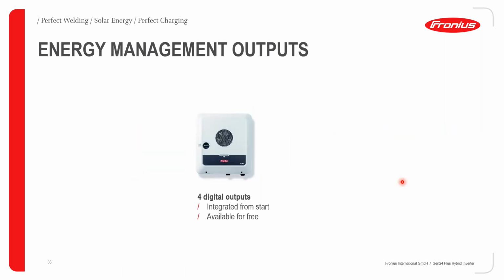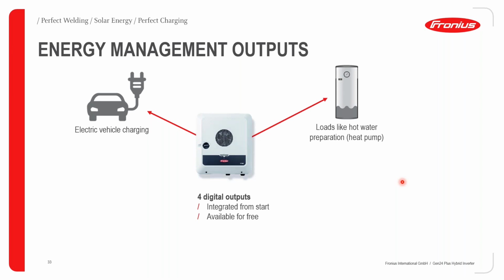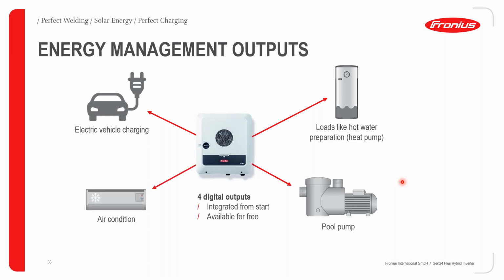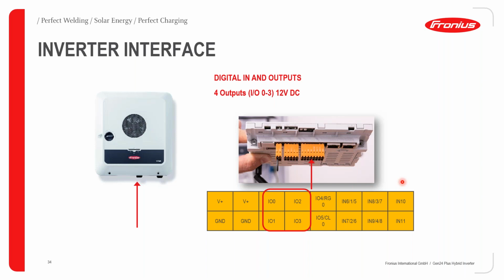Good. So still talking about the energy management, this can be achieved by the use of the 4 digital input-output ports that are already integrated in the Gen24 Plus inverter. These can in turn be used for various applications, which include EV charging, preparation of hot water by using the heating element controller, as I said earlier, we'll be shedding more light on eventually, and operating a pool pump. And then for hot regions, we can also use it to control heavy loads used for cooling, like air conditioners. Like I said earlier, these input-output ports are located on the digital input-output terminals of the Pilot. The Pilot is the designated data communication interface, or card, of the Gen24 Plus inverter.